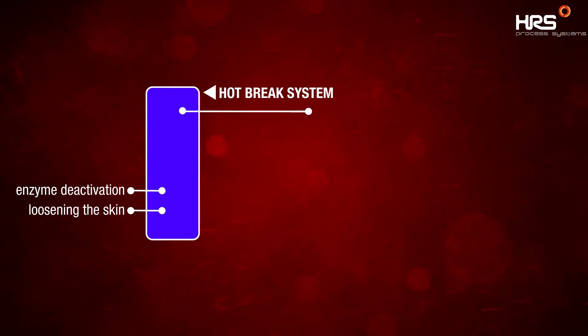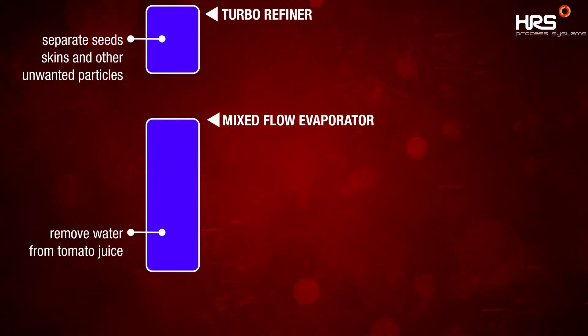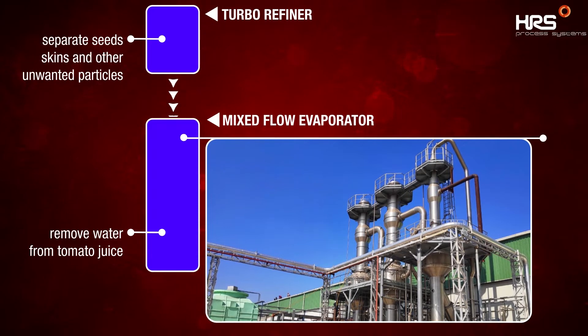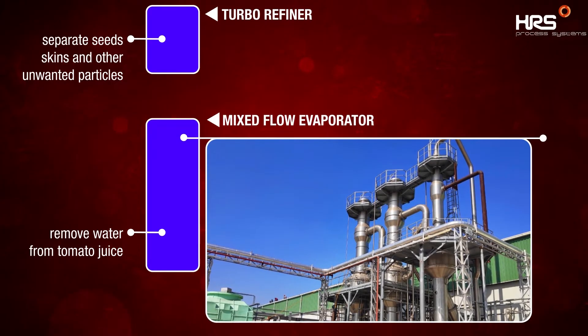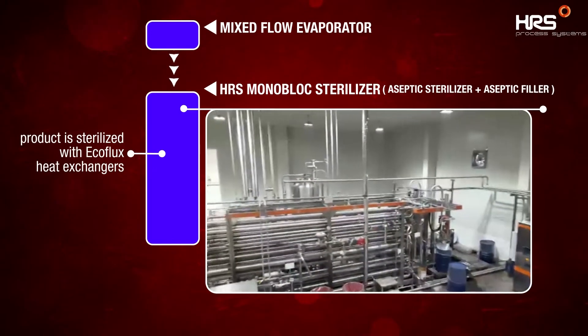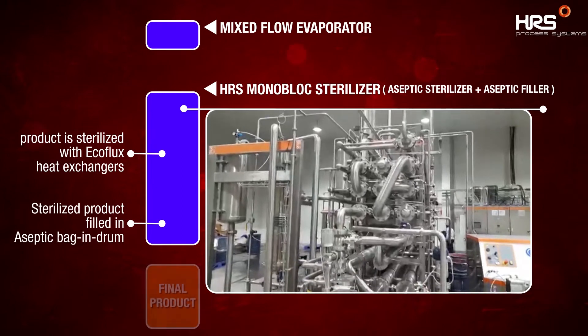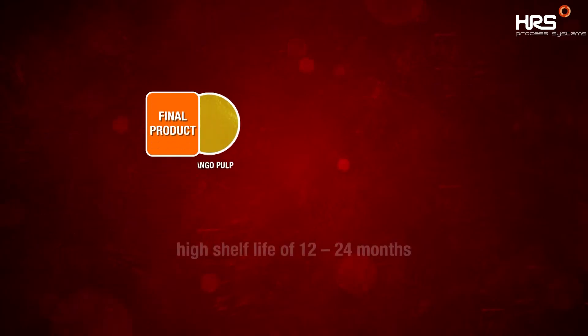Coming back to tomato — to separate seeds, skins and other unwanted particles, the product is sent to a turbo refiner. After separating the unwanted particulates, the refined juice is concentrated through the well-engineered mixed-flow evaporator to remove water from tomato juice. This evaporator is remotely run through touchscreen control panels, programmed and set to desired final brix and water-binding capacity. Concentrated product is then sent into the HRS monobloc sterilizer, an integration of aseptic sterilizer, where the product is sterilized with Ecoflux heat exchangers and an aseptic filler on a single skid. Sterilized product is filled in aseptic bag and drum through the aseptic filler for a shelf life of 12 to 24 months.